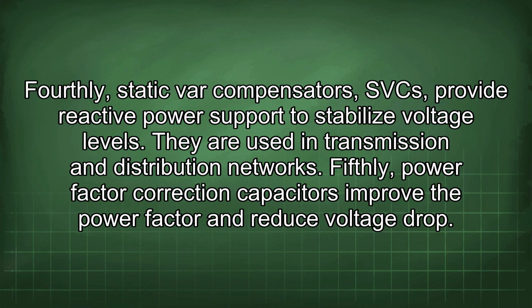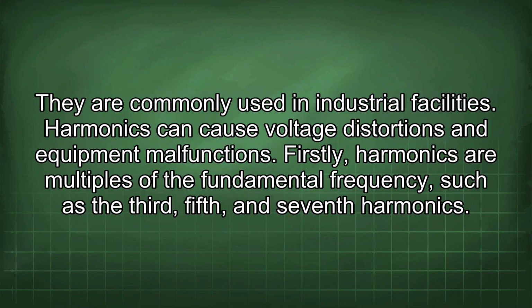Fourthly, static var compensators, SVCs, provide reactive power support to stabilize voltage levels. They are used in transmission and distribution networks. Fifthly, power factor correction capacitors improve the power factor and reduce voltage drop. They are commonly used in industrial facilities.